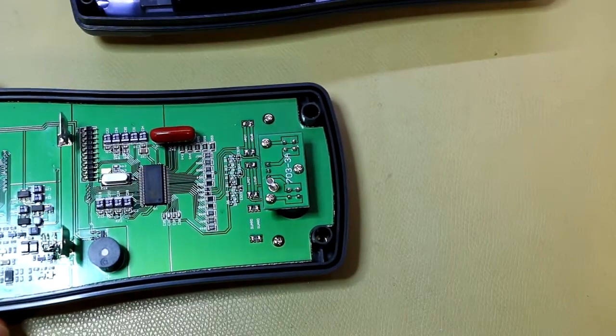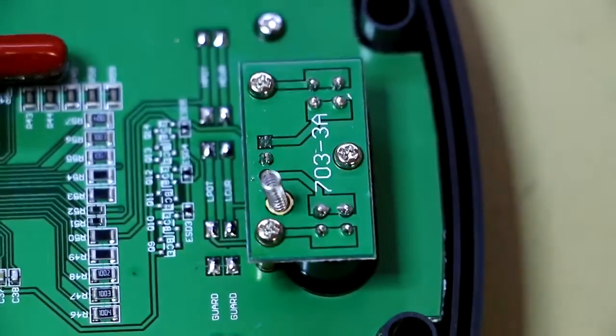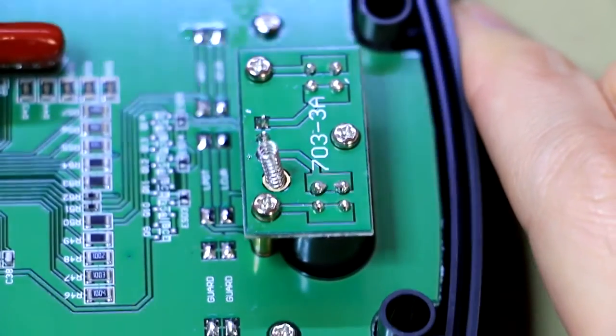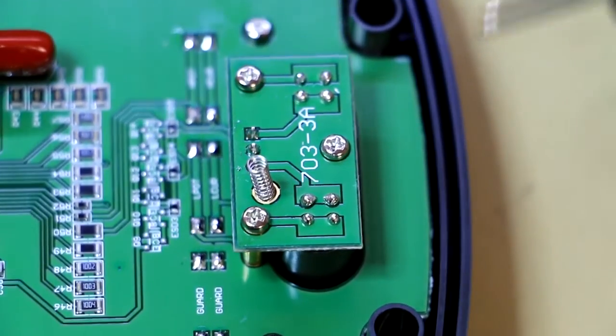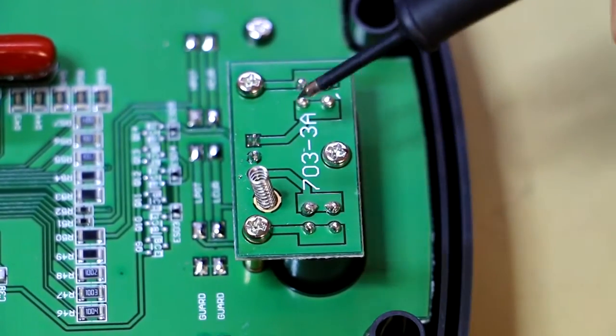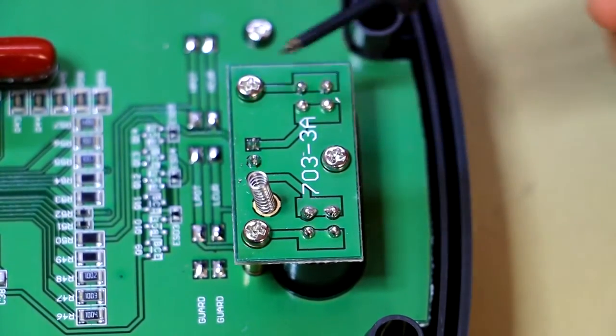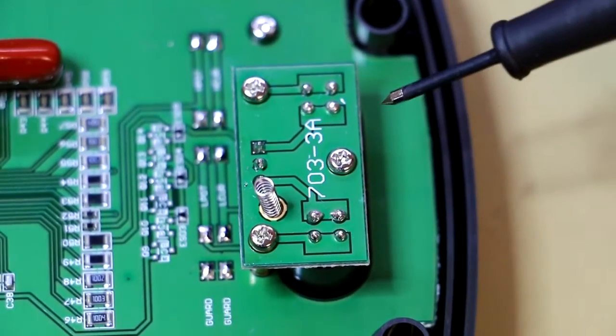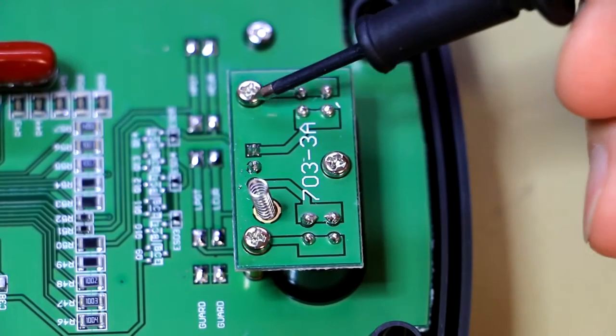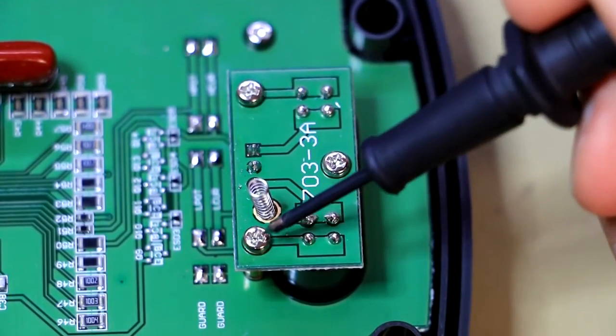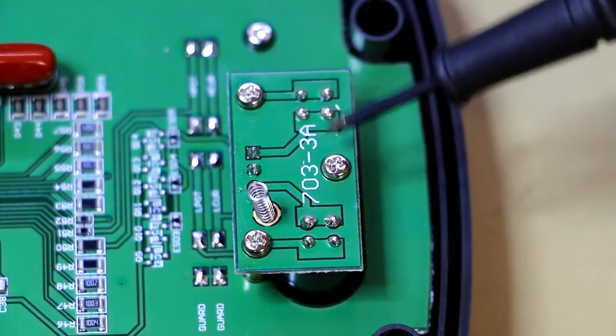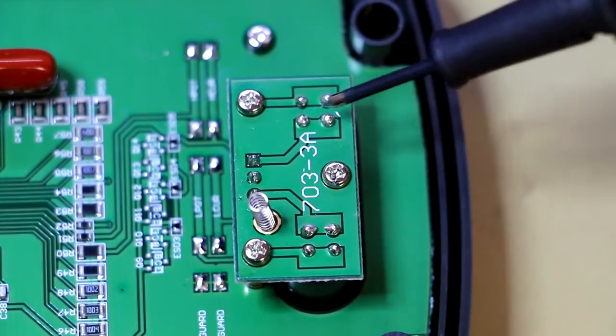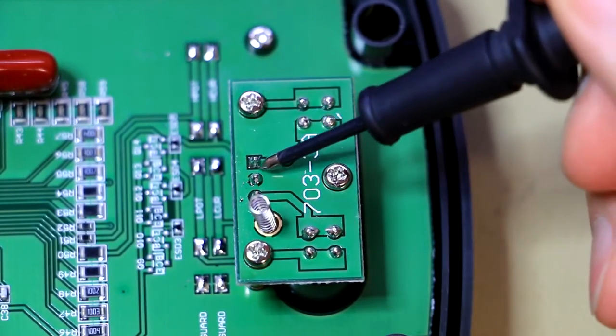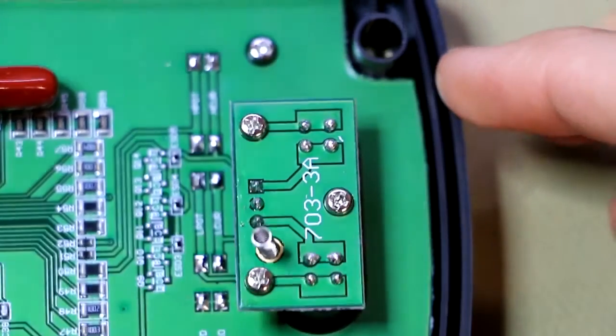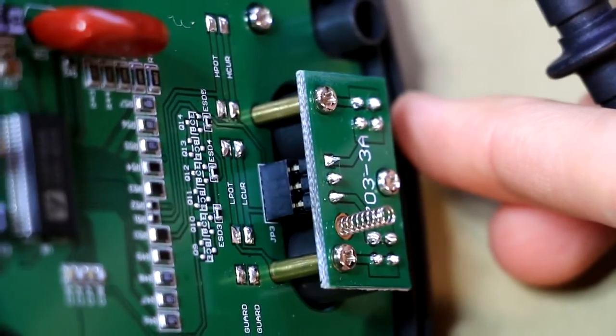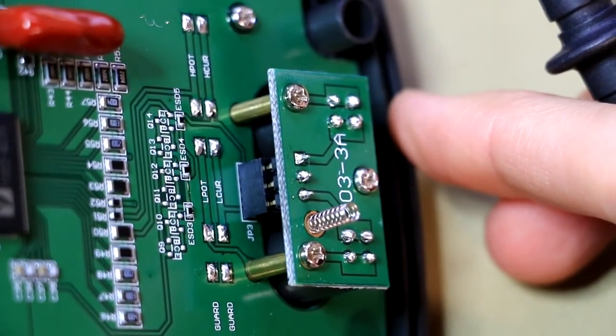Here's the little daughter board for the probes, and actually you can see they repeat this 4-wire measurement capability on this little daughter board as well. So you can actually see here's the current bearing poles, and they combine in the actual probe, and there's the sense wire leading off there, and that's actually just connected with a little header pin connector there.